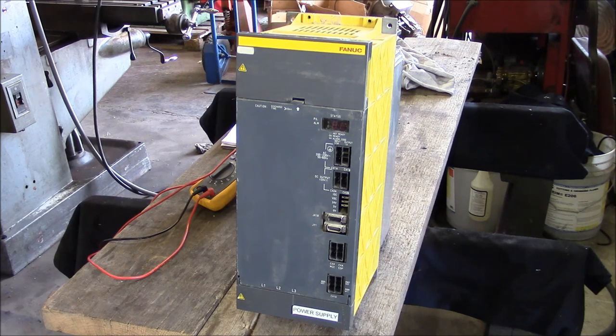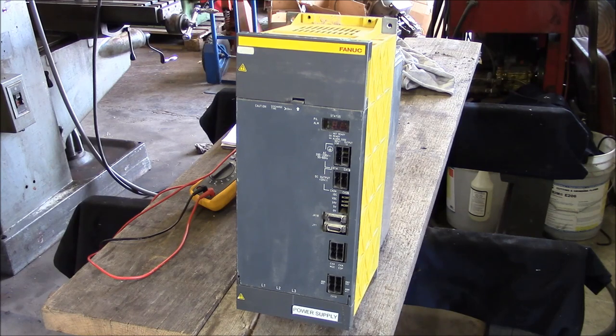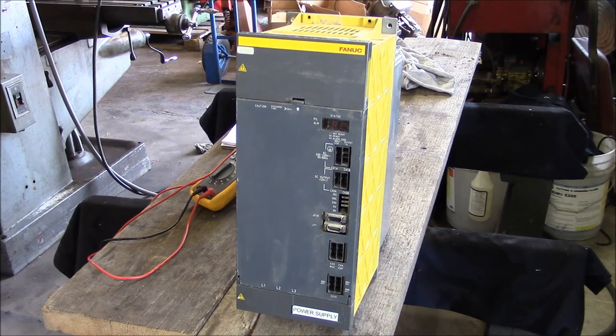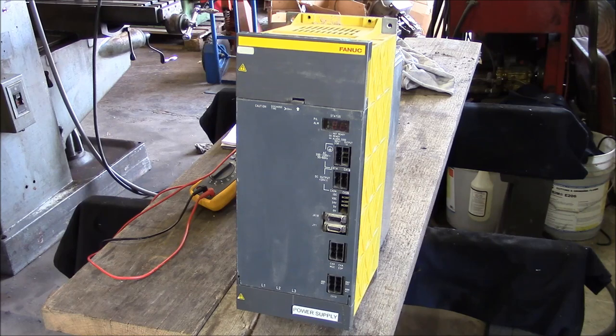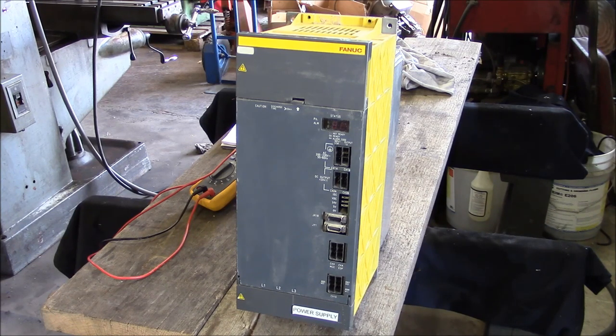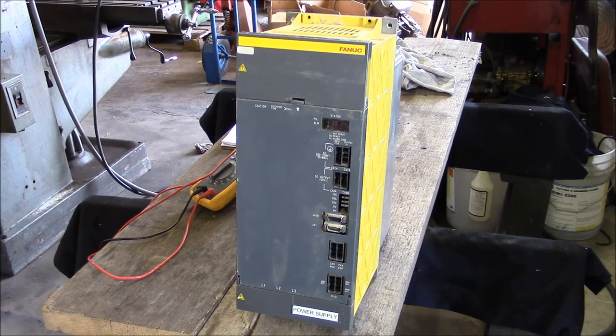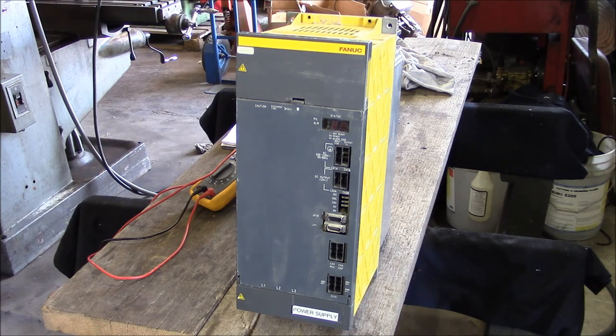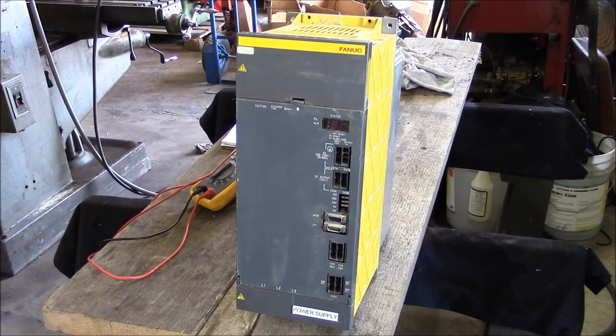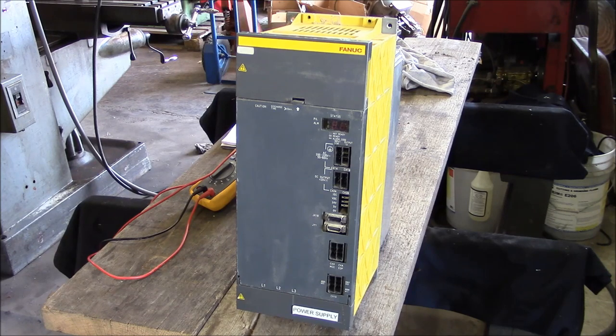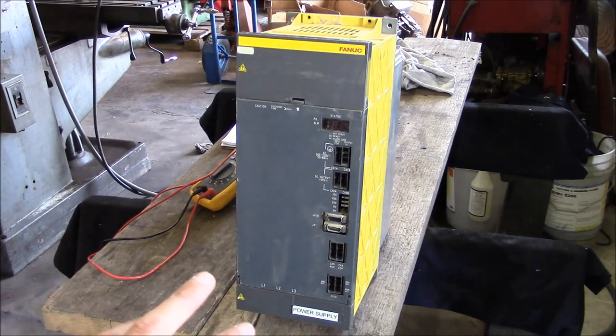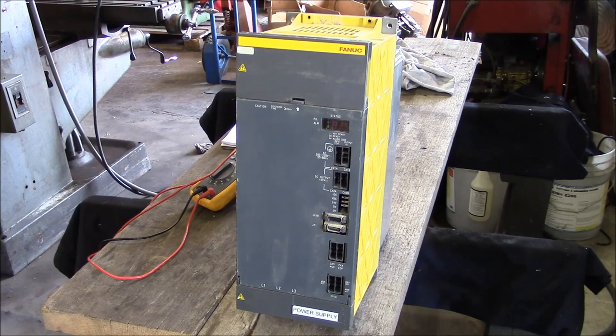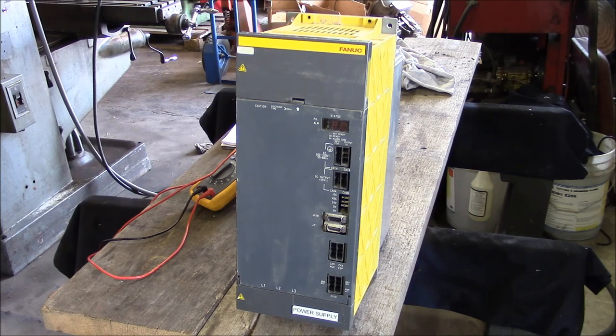Hey guys, welcome back to the shop. Today we are looking at a FANUC power supply, a high voltage power supply. I believe they call this an alpha series power supply, and basically what this is is the DC bus for all the servo drives and the spindle drive. This one has a problem. This is out of a 2000-ish KOMO wood router, and basically what happens is whenever we power up the machine and the main contactor pulls in, it blows the fuses for that supply - the three-phase power to this power supply. So internally there's a problem that's causing a short, basically, and blowing those fuses.